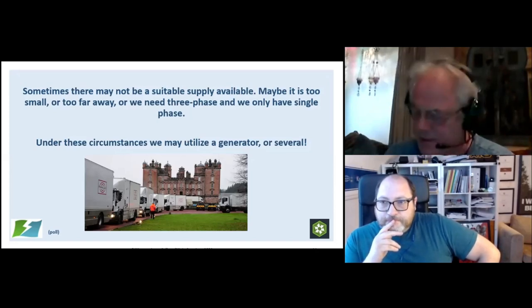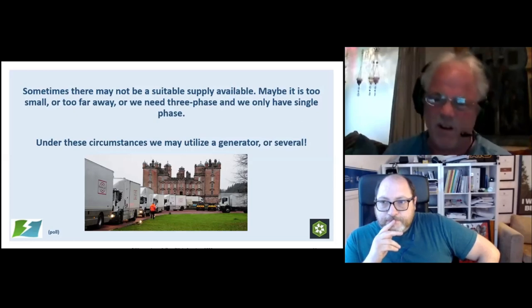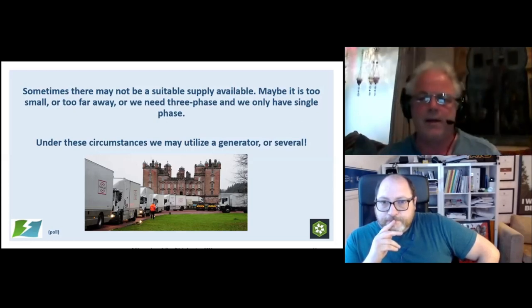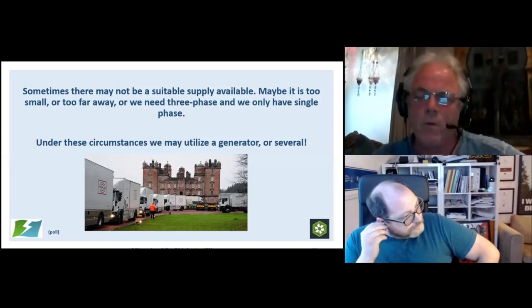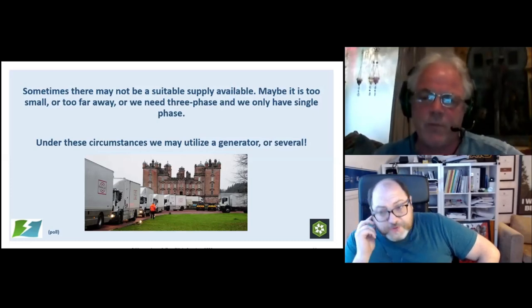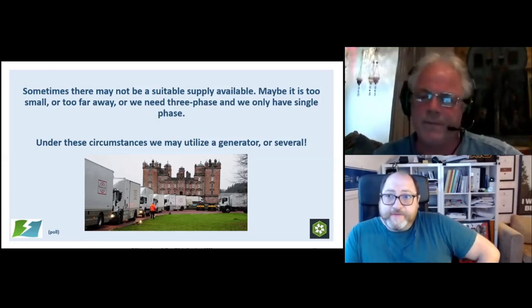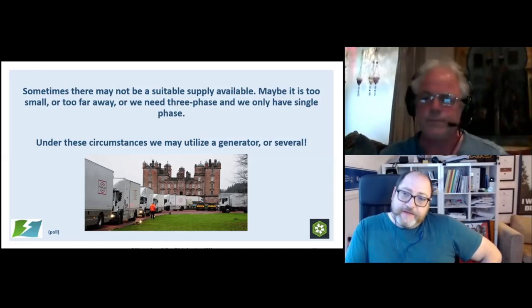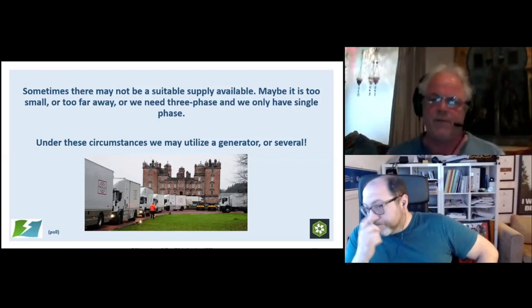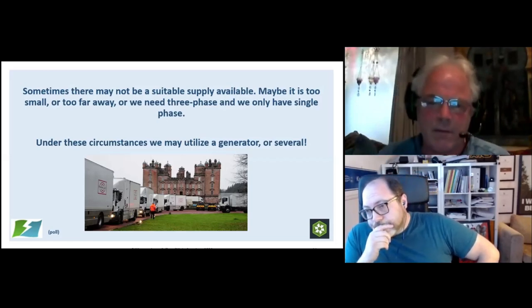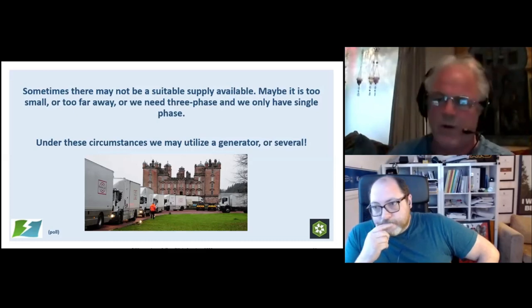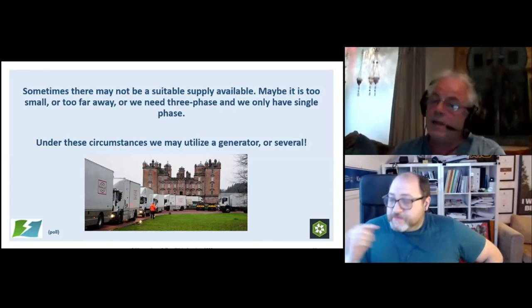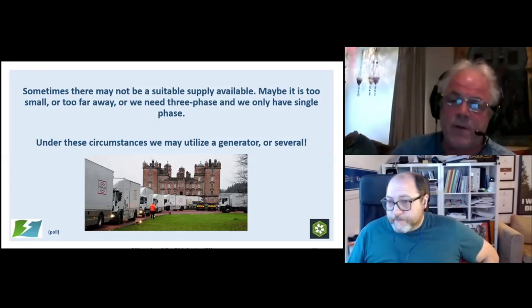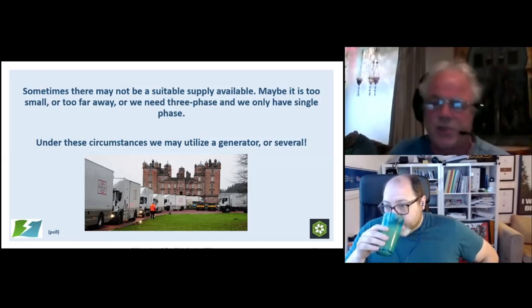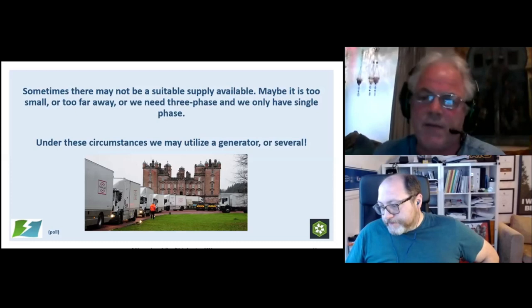So I'm a fan of generators, and I always say to people, rather than relying on whatever shoddy socket outlets you might have sitting around the place, why not think about generators? It also really helps with long lengths. We've gone to many long lengths. Yeah, and this is it. If you've got suitably and sensibly placed generators, then that can save an awful lot of hassle. And cheaper sometimes, with higher costs as well. It is, because you're cutting down on the amount of long lengths of cable you've got to run out, and distro and everything else, and it can actually save you money in the long run.